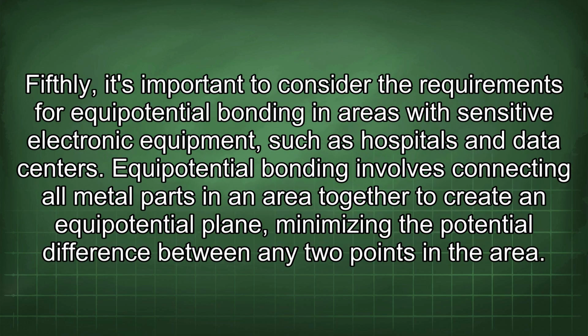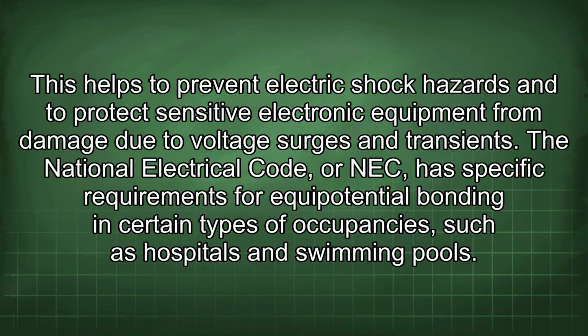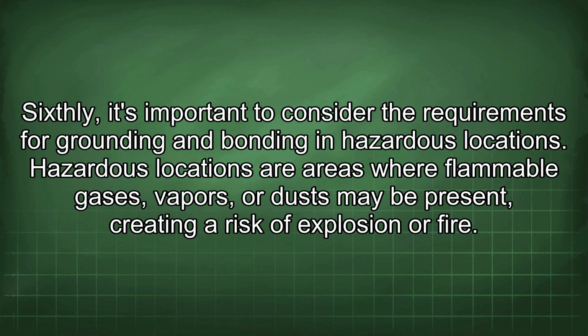Fifthly, it's important to consider the requirements for equipotential bonding in areas with sensitive electronic equipment, such as hospitals and data centers. Equipotential bonding involves connecting all metal parts in an area together to create an equipotential plane, minimizing the potential difference between any 2 points in the area. This helps to prevent electric shock hazards and to protect sensitive electronic equipment from damage due to voltage surges and transients. The National Electrical Code, or NEC, has specific requirements for equipotential bonding in certain types of occupancies, such as hospitals and swimming pools. Sixthly, it's important to consider the requirements for grounding and bonding in hazardous locations.